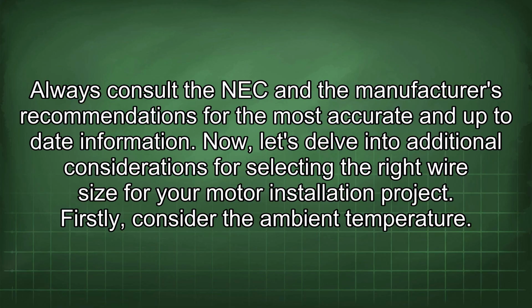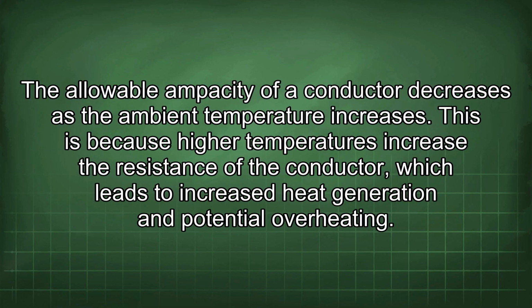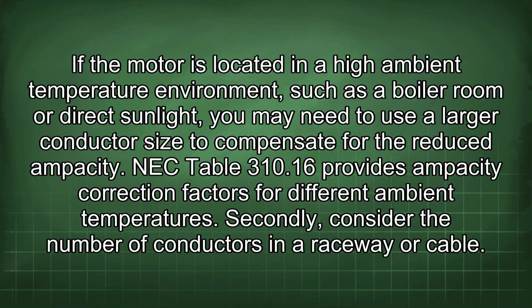Firstly, consider the ambient temperature. The allowable ampacity of a conductor decreases as the ambient temperature increases. This is because higher temperatures increase the resistance of the conductor, which leads to increased heat generation and potential overheating. If the motor is located in a high ambient temperature environment, such as a boiler room or direct sunlight, you may need to use a larger conductor size to compensate for the reduced ampacity. NEC Table 310.16 provides ampacity correction factors for different ambient temperatures.